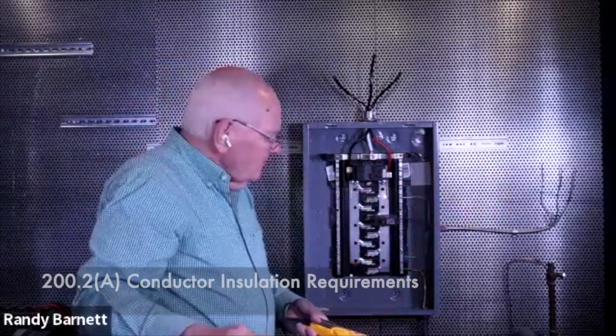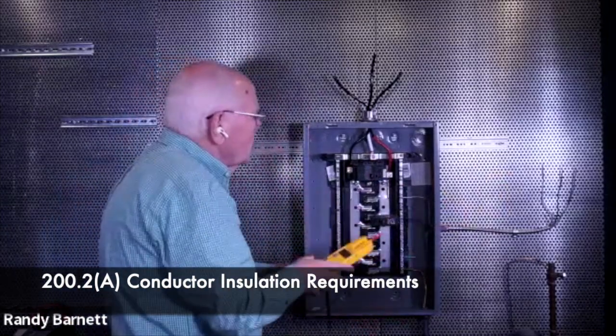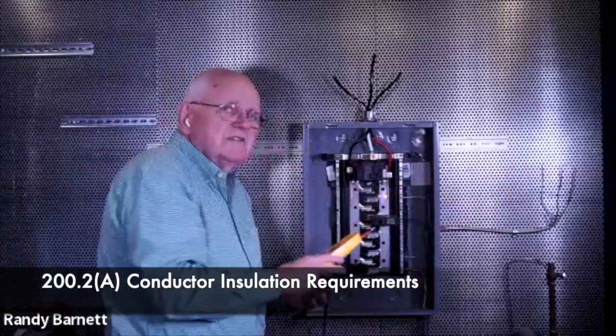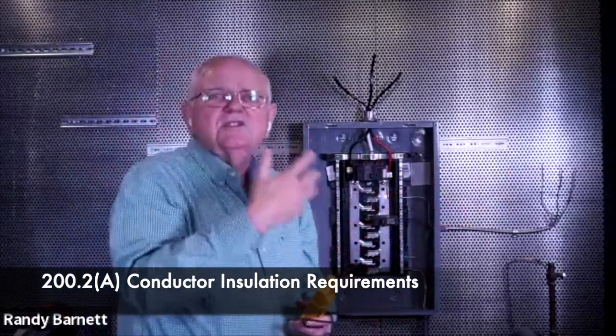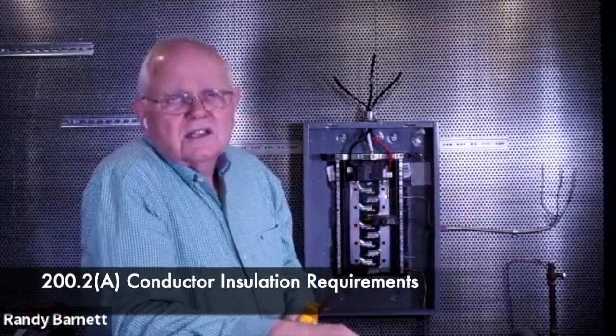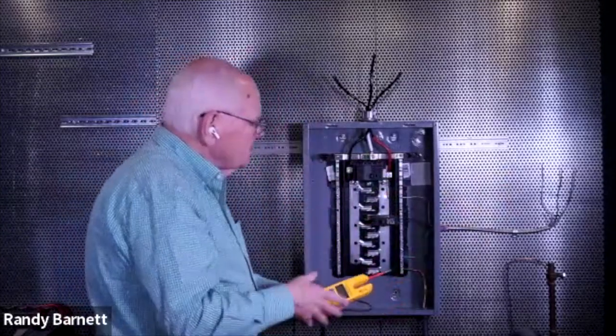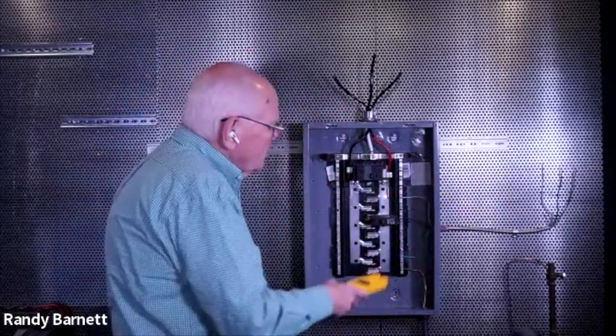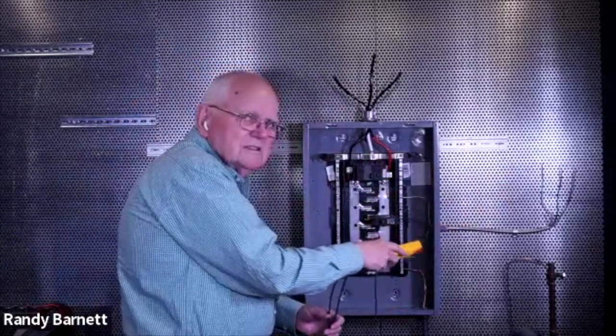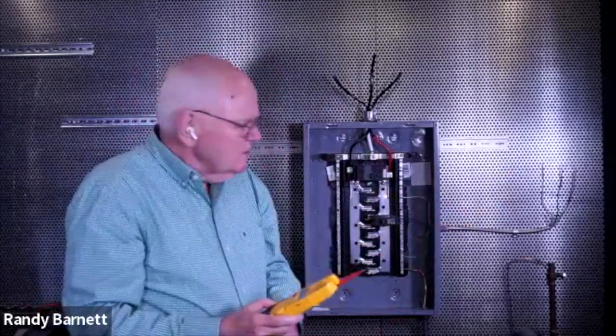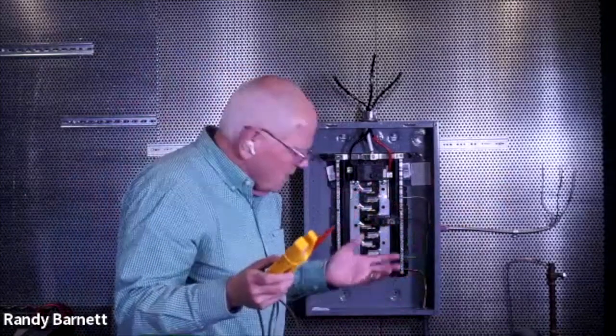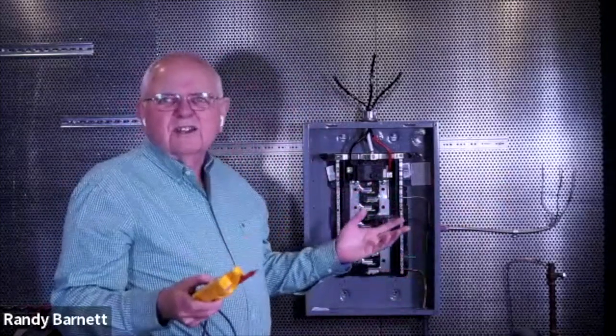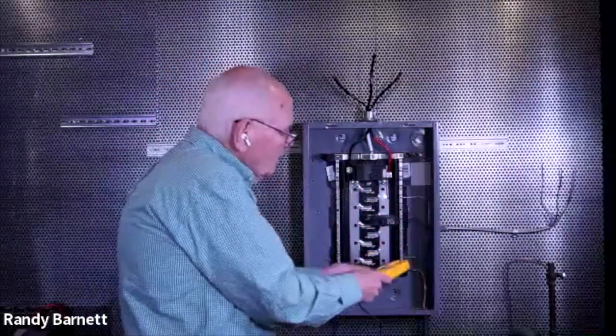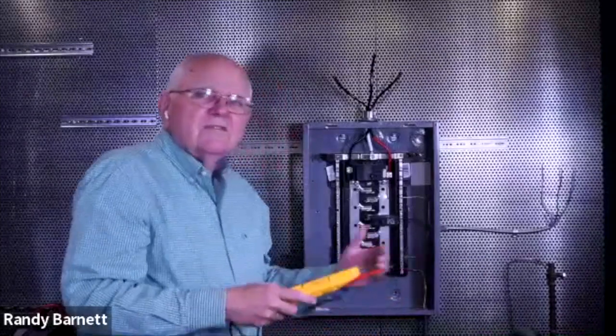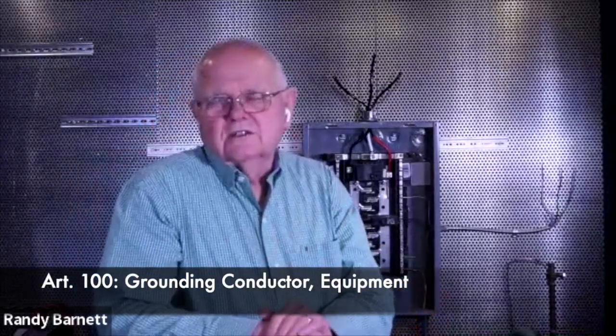So there's current going in and out on these wires 60 times a second then. Now, the insulation for my neutral conductors is going to have to be the same as the insulation of the ungrounded conductors. Let's talk about sizing these conductors. Well, let's talk a little bit first about the rest of the circuit. I've got a green wire down here. Sometimes we call that the grounding wire. That's confusing because they're all connected to ground, or a bunch of them are, except the ungrounded conductors, right? So the green wire, what's the purpose of the green wire? That's the equipment grounding conductor.